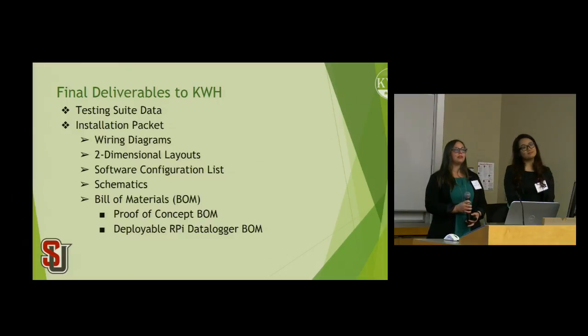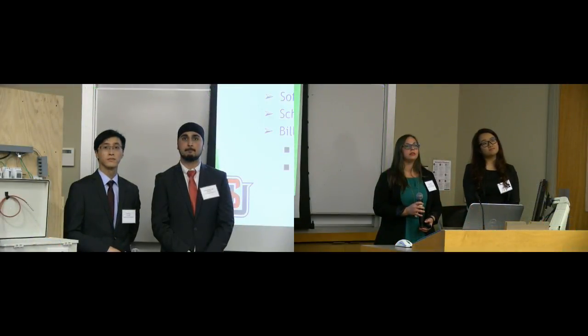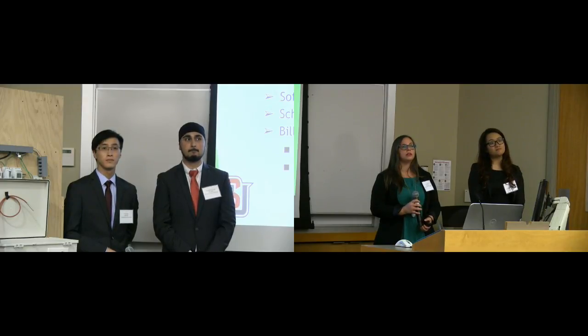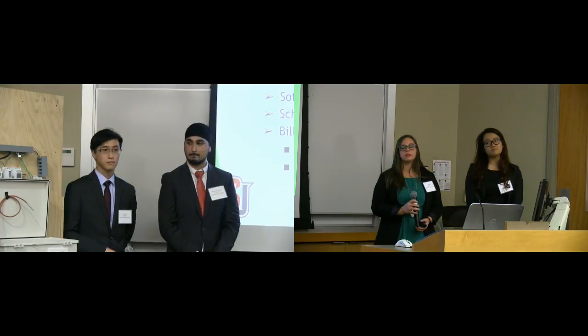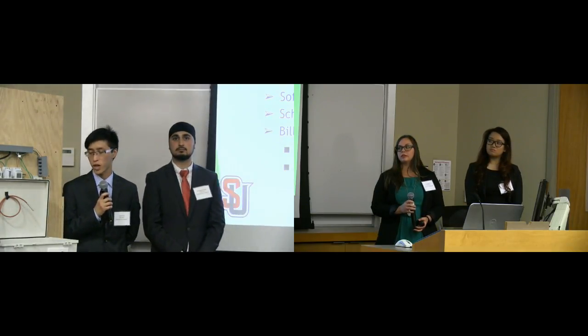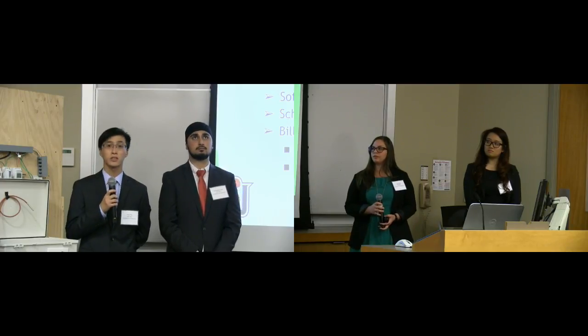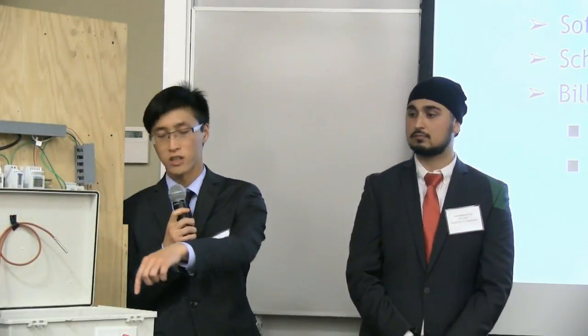Is there any calibration necessary on a new system, to account for sensors or the variation in the resistors and the voltage divider? No, there's no calibration needed for the CTs, Modbus, or temperature sensors. The voltage dividers are already soldered in, so those don't need to be changed, and same for the King Pigeon. The only thing that needs to be changed is the Raspberry Pi configuration for sending to the proper ports. We have two running right now, one in Seattle, which is ours, and one in Denver, which our liaison has. They have different port numbers, so those need to be changed appropriately.